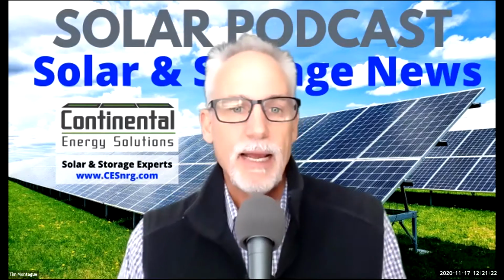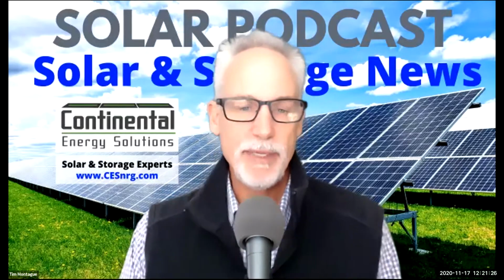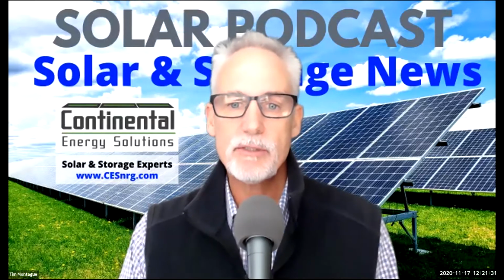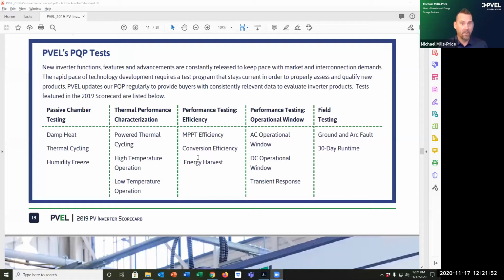Okay. And then there's a nice table on PVEL's PQP tests, passive chamber testing, thermal performance characterization. Let's walk through that. So again, we're performing lab tests and we're trying to do it in a commercial practice. So we have to do accelerated aging tests if we're going to try to project how long the product will last. So we're intentionally putting it in conditions that are at the maximum end of the ambient temperature window, or even above that for some of these tests.